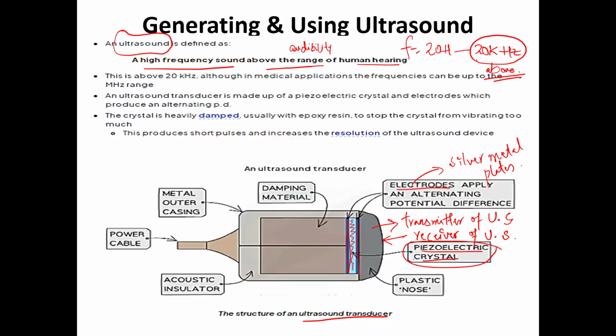Next to it there is a damping material. Why is there a need for a damping material? Just to control the frequency of the piezoelectric material. There is a plastic nose, the surface of the transducer. The back outer part is made of metal casing, and there is a power cable going to the ultrasound machine. Inside the casing there is an acoustic insulator, whose purpose I will explain later. So this is the basic structure of the ultrasound transducer.